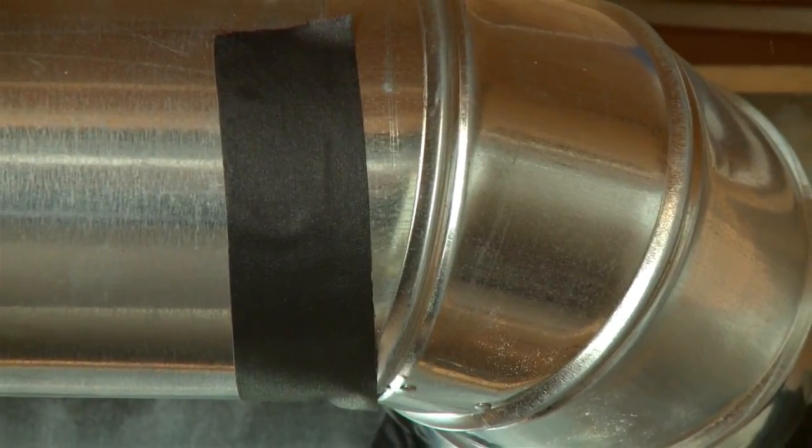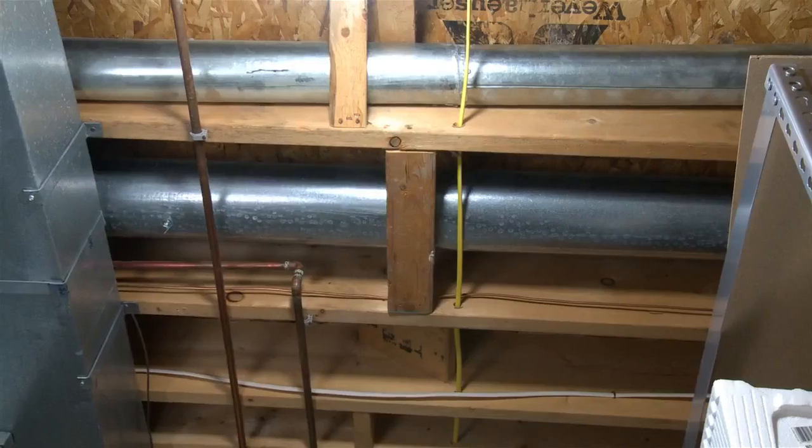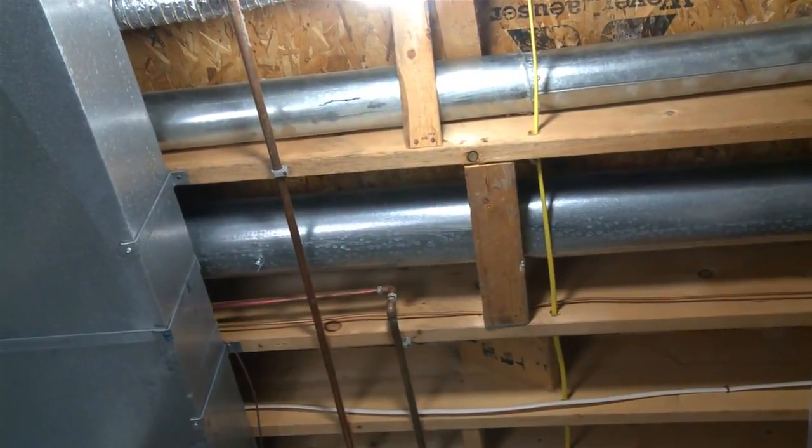It's not limited to what's behind the drywall, it's not limited to what's behind the refrigerator. All of the ductwork gets 100% sealed, as opposed to a manual system which allows you to do only what the eye can see. I've known about AeroSeal for the past 12 to 15 years, since it first came out, and I'm a huge fan of it because that technology allows the ductwork to be sealed from the inside. With conventional duct sealing, you would use a mastic and would have to physically get to all the gaps, joints, and holes in the ductwork, and in many homes that's impossible, whether it be a finished ceiling or ductwork going up a wall, whereas AeroSeal will seal all the ductwork from the inside.